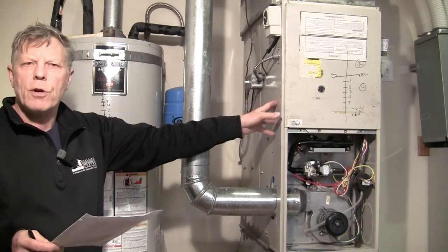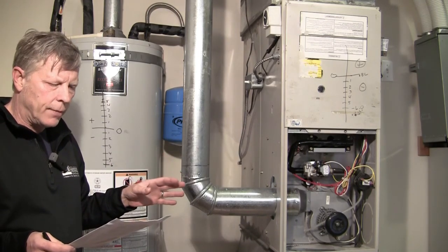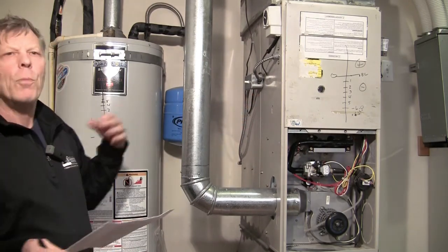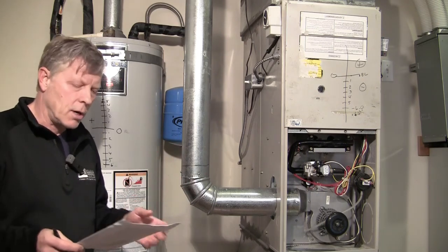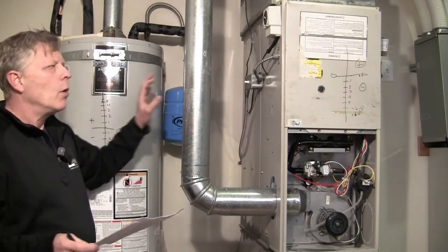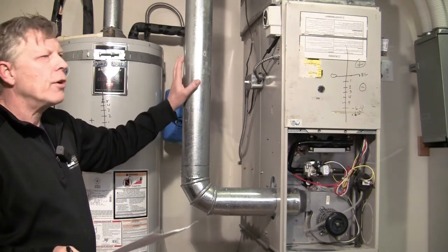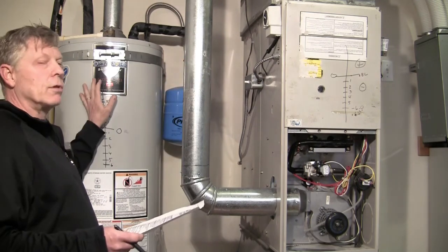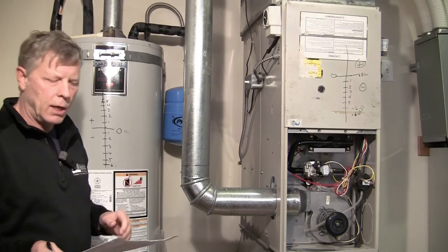We're going to give these things estimated efficiencies. Generally, we just give the furnaces and boilers efficiency ratings, because we're going to put that into our computerized energy audit. We also have to determine if they're open or closed, because open combustion appliances are more susceptible to backdrafting, whereas closed combustion appliances aren't. And then whether they share venting, because what we have here is a water heater and a furnace that are sharing venting. If this furnace wasn't sharing the venting, we wouldn't do a spillage test on it. But since it is sharing the venting with the water heater, we are going to do a spillage test on it. So it's very important that we understand the difference.